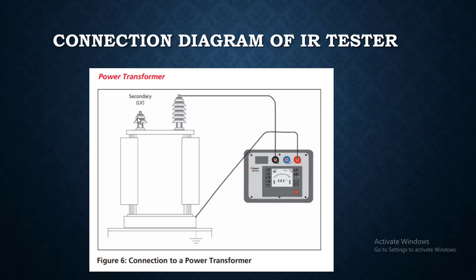Another option could be to ground the LV as well, so in this way you can test the insulation level together from HV to LV to ground.